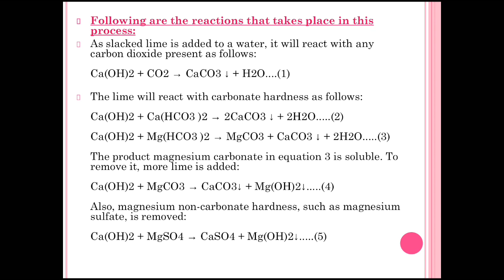The product magnesium carbonate (from equation 3) is soluble, so to remove it more lime is added. When magnesium carbonate remains in water, excess lime (calcium hydroxide) is added so it reacts with magnesium carbonate, giving calcium carbonate precipitate with removal of magnesium hydroxide precipitate. By using the maximum amount of lime we can remove magnesium carbonate type of impurity.